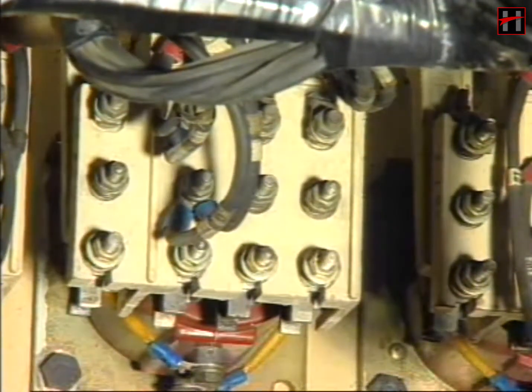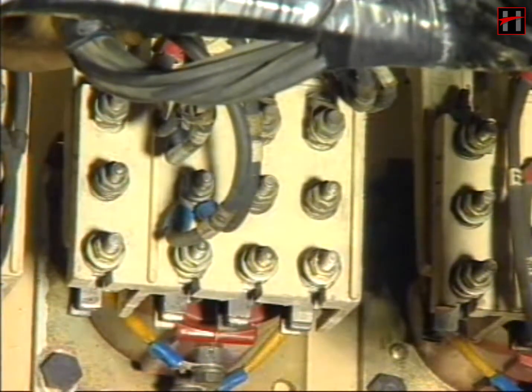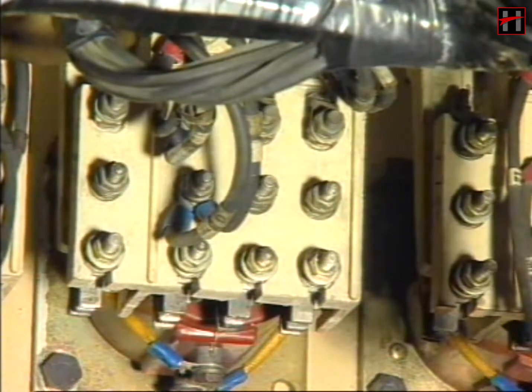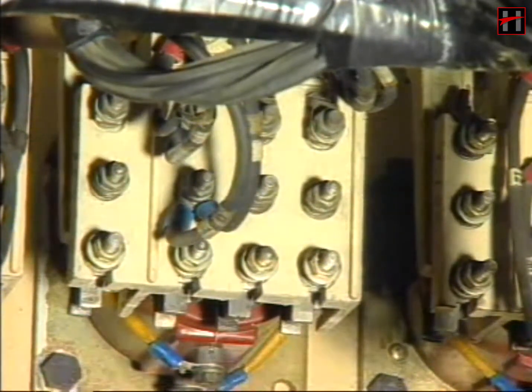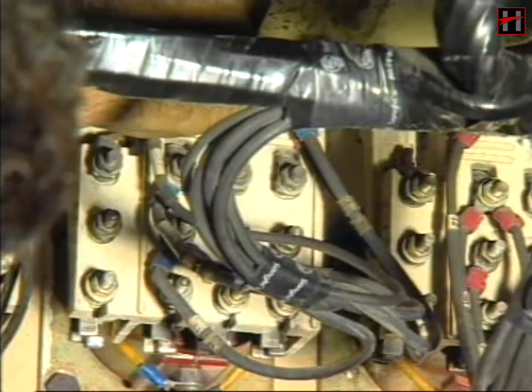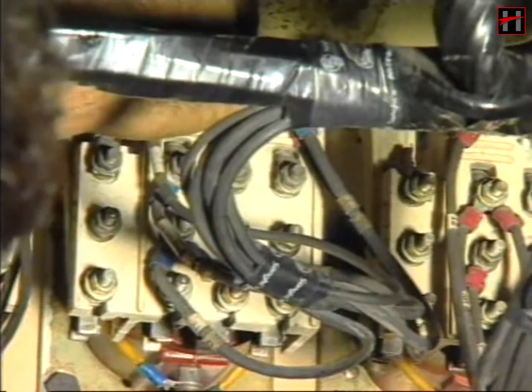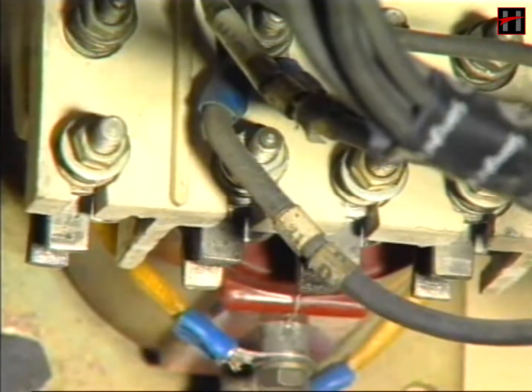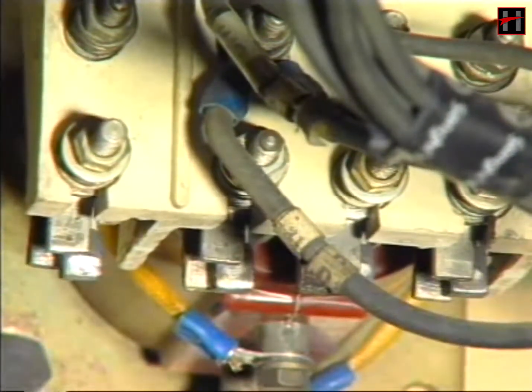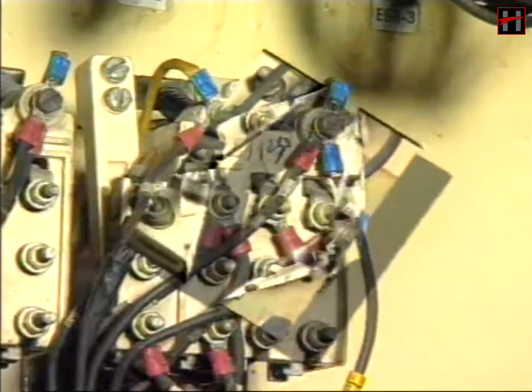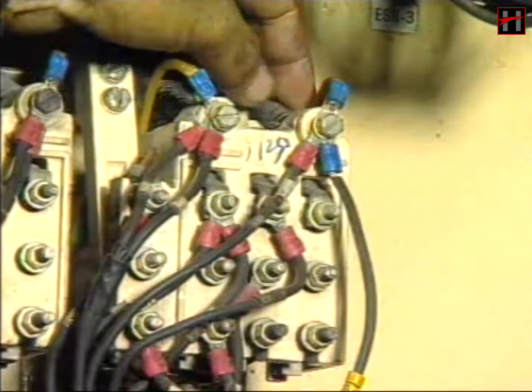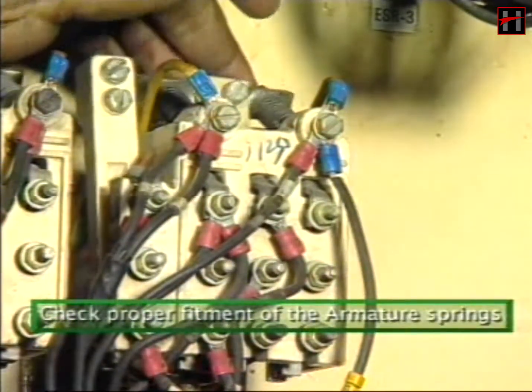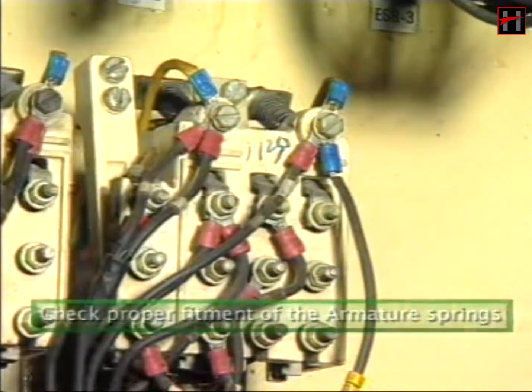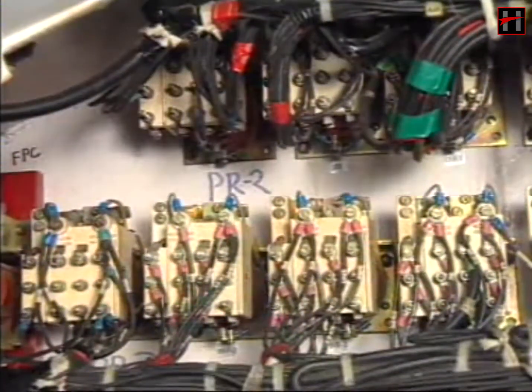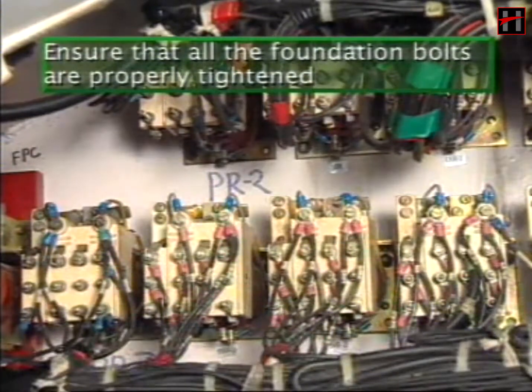Operate the relay manually and ensure proper alignment of the relay contacts. If the contacts are not aligned properly, change the relay. Check the overtravel of the interlocks. If the contact gap of the interlocks is not proper, replace with a new relay. Check and ensure proper fitment of its armature spring. Ensure that all the foundation bolts of the relays are properly tightened.